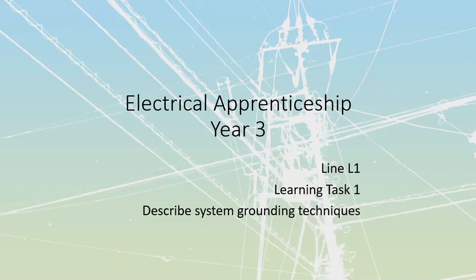A, we're going to provide a complete path for fault currents that will then be created whenever a system faults. There's no fault current, but as soon as it faults, it will create it, and there will be a complete path. B, we are going to deliver that fault current back to the supply transformer, either through a line or through a neutral. And then C, we're going to allow the associated device, an overcurrent device, like a breaker or a fuse, or an alarm type, to sense that fault and respond. It's not always going to be an overcurrent, and it's not always going to be an alarm type. There's different applications for them.